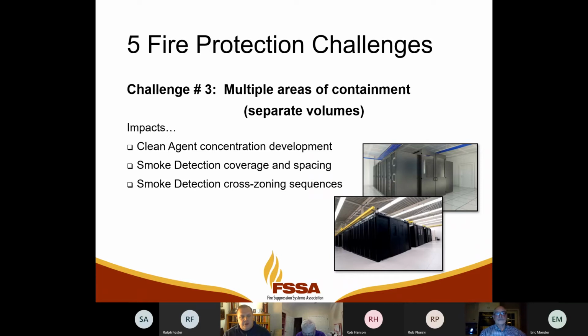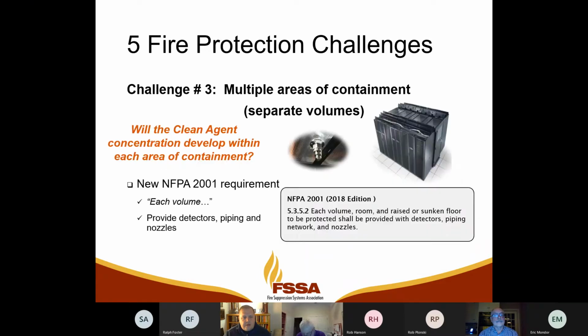Challenge 3 here: multiple containment volumes. All of a sudden we're taking one large space and making smaller volumes. How do we deal with that? How do we deal with it from a clean agent concentration development standpoint? Smoke detector coverage: now there's a volume within a volume. How do we cover that? And can the volumes break up our cross zoning? In a lot of suppression releasing, we use the idea of cross zoning, where it takes multiple smoke detectors to detect smoke before we'll release a system. And can these new obstructions affect that?